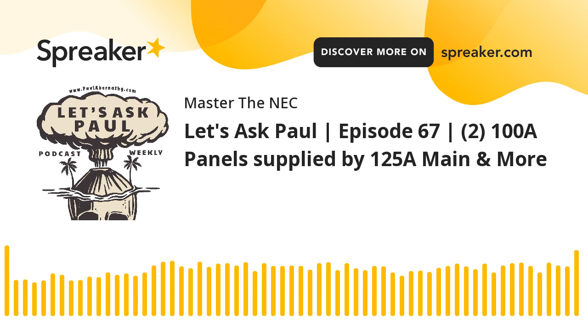But when it comes to this rule, obviously you're talking about a service. This rule was added in Article 230, and it was added during the 2020 cycle and is located at Section 67 of Article 230, and it says surge protection. And you've got an A, B, C, and D here. You have to follow each one of them. And this is an example of a retroactive type of rule. If you go in and, for example, the service equipment is replaced at some point, then you're going to apply this rule. Okay? So we'll look at it so we can break it down for you.